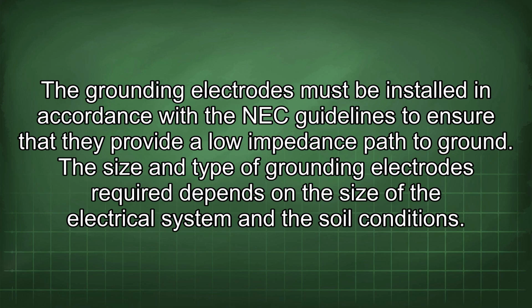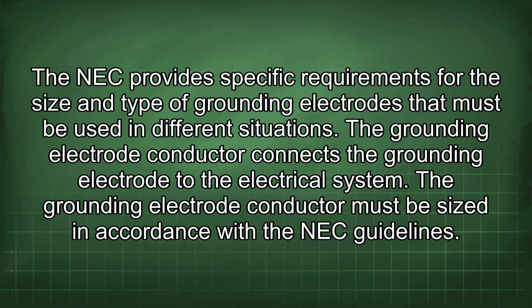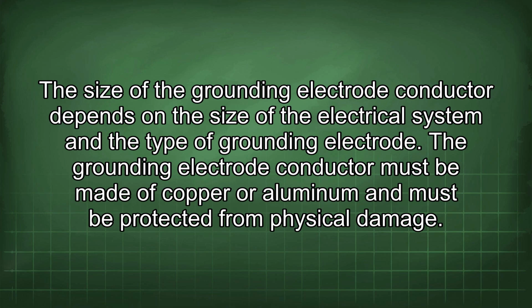path to ground. The size and type of grounding electrodes required depends on the size of the electrical system and the soil conditions. The NEC provides specific requirements for the size and type of grounding electrodes that must be used in different situations. The grounding electrode conductor connects the grounding electrode to the electrical system. The grounding electrode conductor must be sized in accordance with the NEC guidelines. The size of the grounding electrode conductor depends on the size of the electrical system and the type of grounding electrode. The grounding electrode conductor must be made of copper or aluminum and must be protected from physical damage.